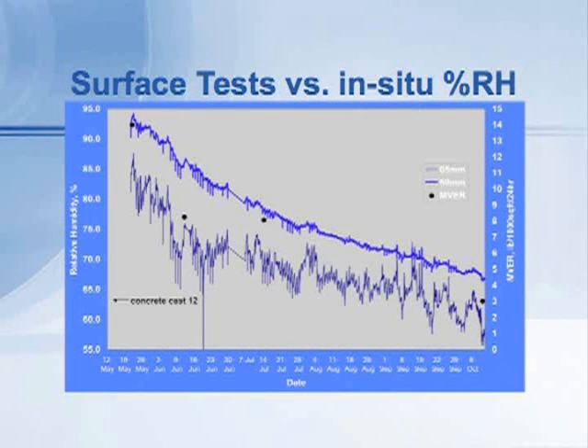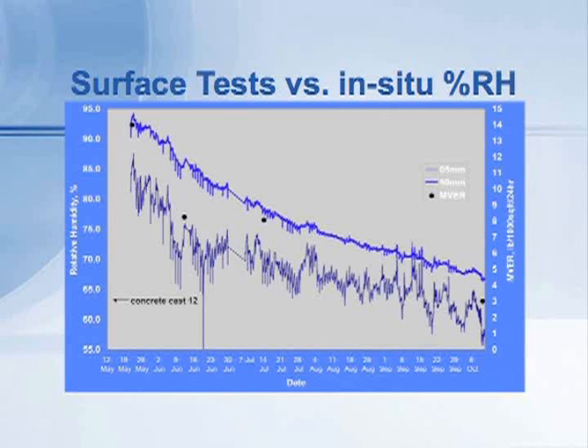I want to talk about the difference in results in a little more detail between surface tests and the in-situ probes, and why it is important to put the probes at the correct depth into the concrete. This graph shows the relative humidity on the left-hand vertical axis versus time across the bottom. These are measurements made in a slab here at our facility several years ago, over the course of about five or six months — the dates at the bottom run from May through October, and the relative humidity runs from about 95 percent down to about 55 percent. The top blue line shows the relative humidity at 40 percent of the depth of the slab, going from about 95 percent when the slab was first cast down to about 65 to 70 percent after five or six months. That's the typical sort of measurement you will find in a concrete floor slab if you follow it over time.